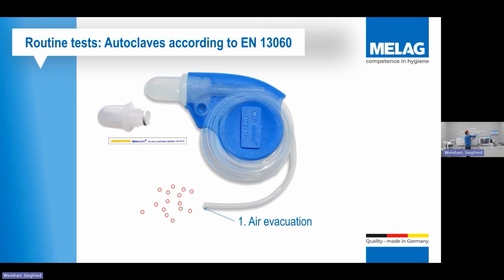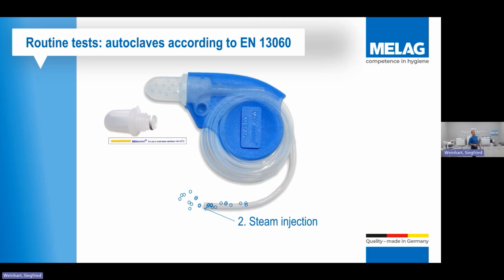Your autoclave will have either a steam penetration cycle or a Bowie Dick cycle, is what they tend to be. What will happen is a vacuum will pull, and what that vacuum is doing is it's evacuating all the air from the inside of that 1.5 meter tubing. Steam is then injected down that 1.5 meters of tubing right the way to the very end, where you have your little control strip that sits in that end. That little control strip is looking for a temperature, 134 to 137 that you can see on there. And it's also looking for time as well.